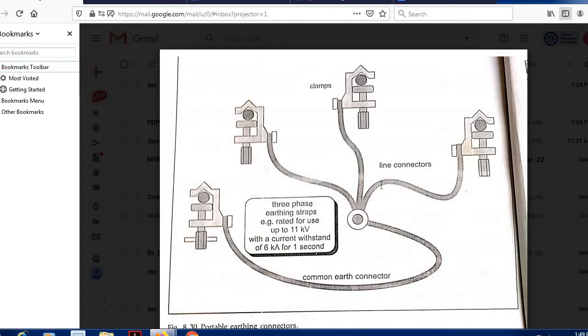The terminals that we are going to connect to the equipment or to the circuit where we want to check the insulation resistance. After connecting this earthing strap, we then connect, again through a long insulated handle, the probe of this Megger to the point where we are going to check. So between the 2 conductors or between conductor and earth, we connect those Megger probes, through an insulated long handle.